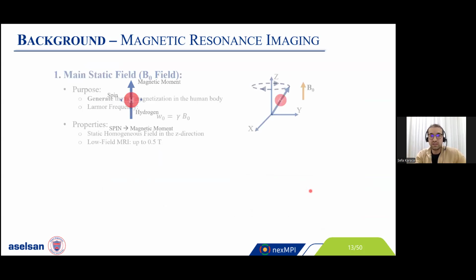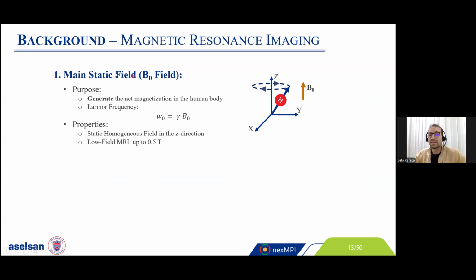In the case of magnetic resonance imaging, however, we try to image basically the hydrogen atoms by using the different relaxation times. In order to perform MRI, we need to generate first the main static field, also called the B0 field. We use this field in order to generate the net magnetization in the human body. It's a static, homogeneous field in the Z direction, and the homogeneity of the B0 field is quite important for MRI. As you can see in this equation, the Larmor frequency is directly proportional to the B0 field. And in the rest of the presentation, I always said that we are performing low field MRI. Low field MRI means that this B0 field strength is up to 0.5 Tesla. I've already shown you two different hybrid MPI MRI scanners, and they're also in the low field MRI regime.